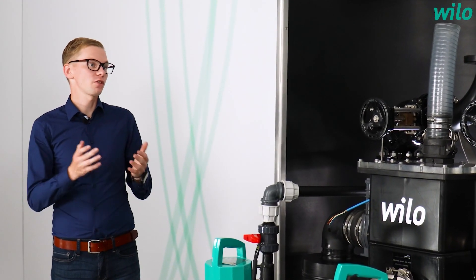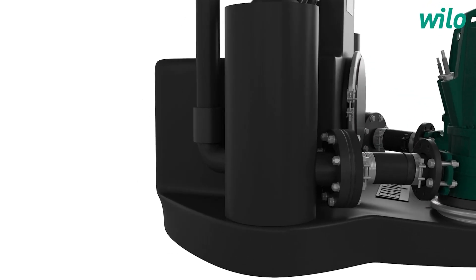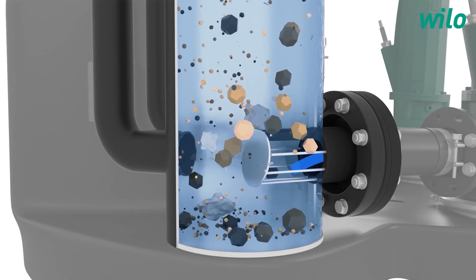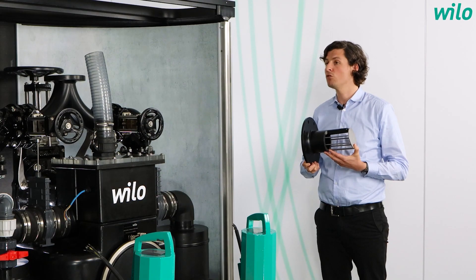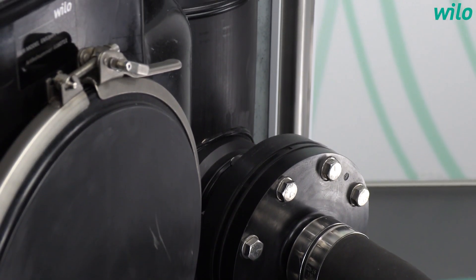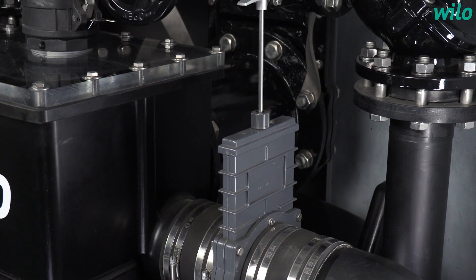Let us talk about these three points. How does the system prevent clogging and ensure operational reliability? With a solid separation system, the coarse solids in the wastewater are firstly separated and held back in the solid separation tanks with our unique mechanical grille, which I can show here. Only the pre-filtered wastewater is allowed through the pump hydraulics and into the collection tank. When the pumping process starts, the wastewater is pumped through the solid separation tanks and into the outflow, taking away the coarse solids with it. This increases operational reliability.